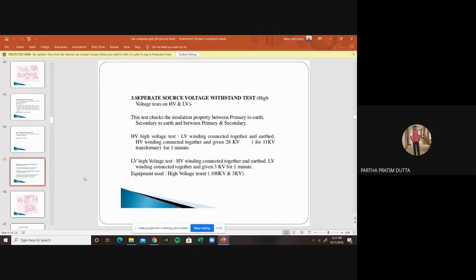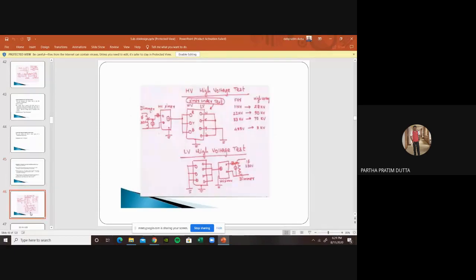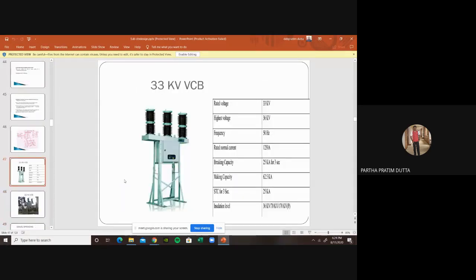Then a separate source voltage withstand test. It is a very good, important test. This test checks the insulation property between the primary, I mean HV to earth, secondary to earth, and HV to secondary. What we do here is LV winding connected together to earth, HV winding connected together, and we give 28 kV for 1 minute. The same we do for the LV test, but with 3 kV for 1 minute. The equipment is a high voltage tester, and this particularly gives us an idea about the insulation leakage current. This is the circuitry of the LV and HV high voltage system, how we do that. Because of shortage of time, I don't want to explain it much more. A 33 kV VCB is there. It is how it is placed in a marshalling box.